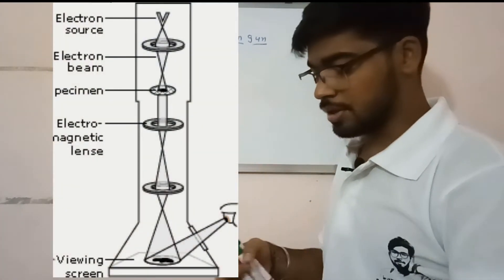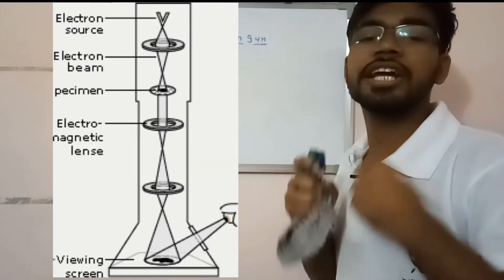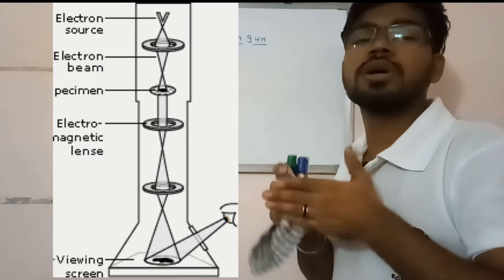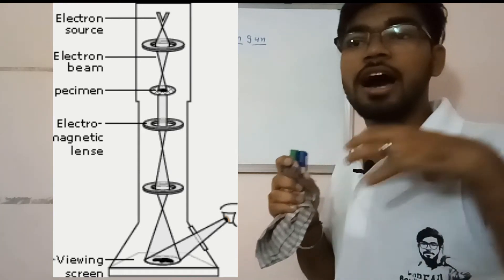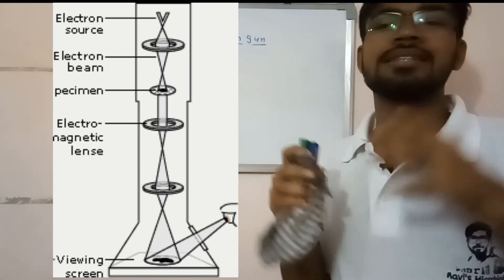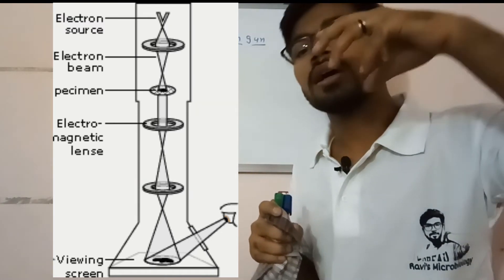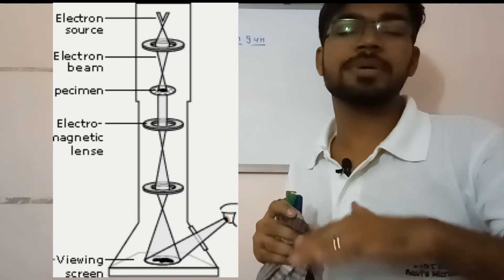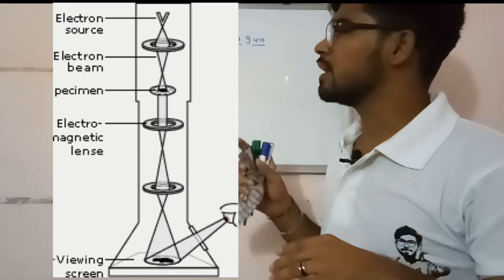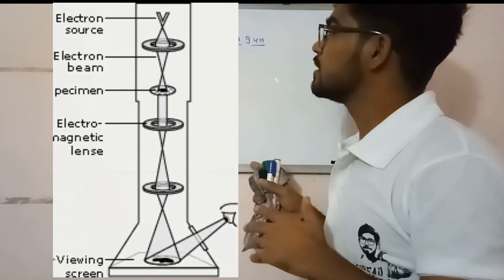As you can see in the image, the microscope is inverted. The electron gun is heated and generates an electron beam. The electron beam is straightened and comes through the anode. Accelerating voltage gives a higher and stronger powered electron beam to bombard. Through electromagnetic lenses, it bombards into the object and transmits through the object. The image is formed on the fluorescent screen which is held below the microscope. This image is shown by the computer or camera.